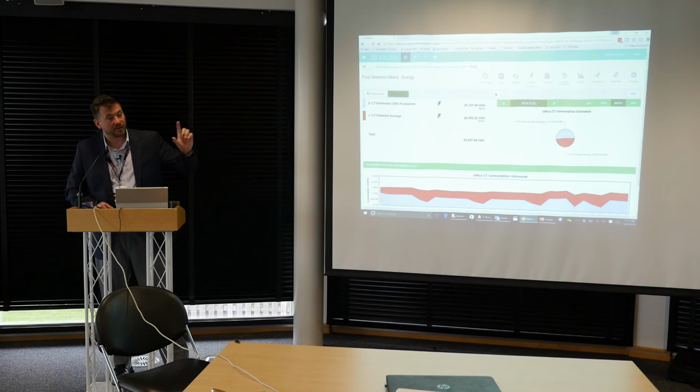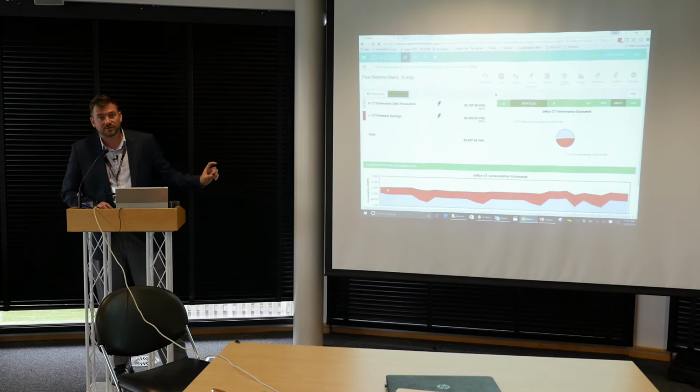And we imported in the performance curve of new pumps. So we had some pumps in mind that we said these are variable speed pumps that you should use. At the same flow rates, those pump curves were imported, and at the same flow rates being demanded by the building, that's what the energy used would be, which is what's blue. So essentially the red is what you would save every month.